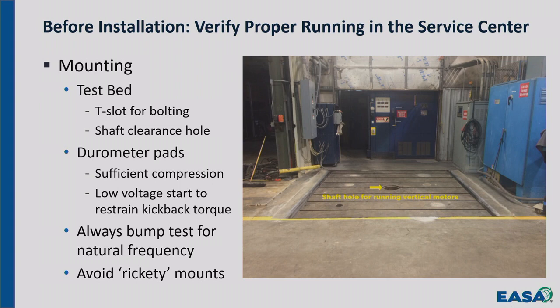Okay? Fundamentally, you put a vibration transducer on the machine that can measure frequency of vibration and amplitude of vibration, and you take a mallet or a block of wood or a rubber mallet and you wallop the machine in the same direction the transducer is mounted, and you let it vibrate. And you measure that frequency of vibration and you determine its natural frequency. Okay? These vertical motors, most of them, any large one of significance, come from the manufacturer with a known reed frequency. The reed frequency is what frequency it vibrates at when it's bolted down. So that's the motor reed frequency.